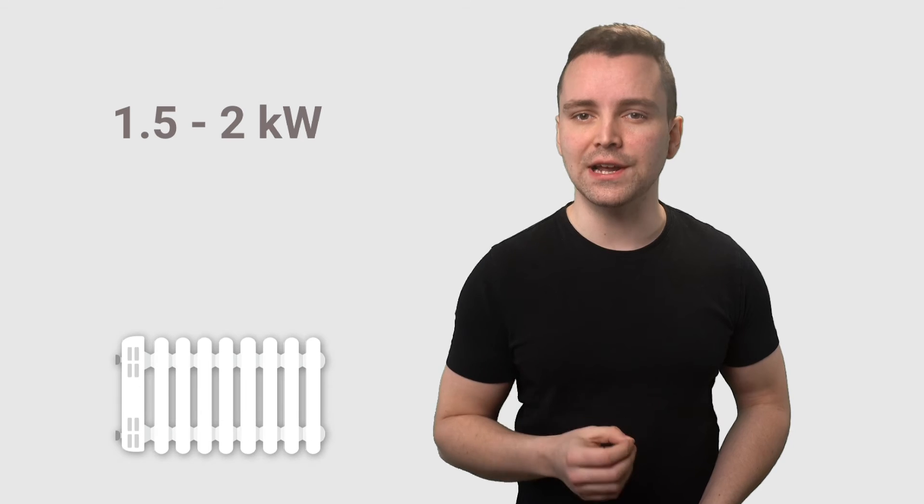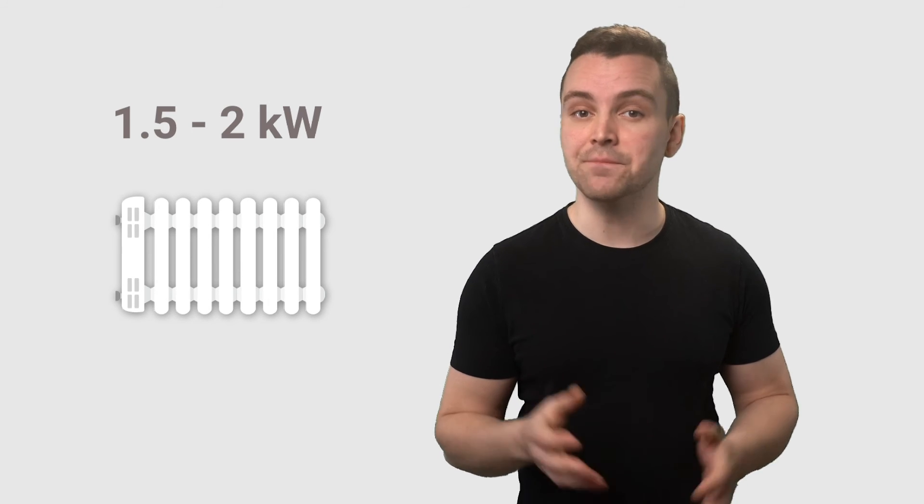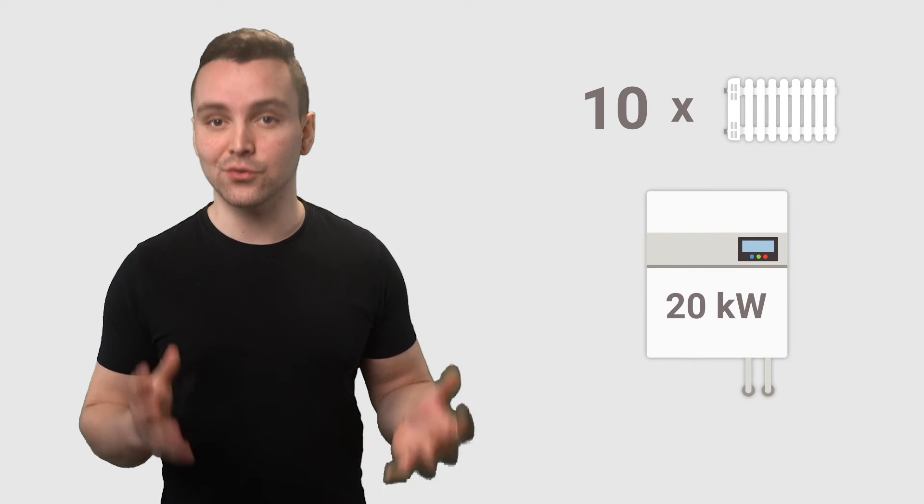A good way to work out what output size is best for your home is to allow for 1.5 or 2 kilowatts for every radiator in your home. For example, a home with 10 radiators would need a boiler with an output of around 20 kilowatts.